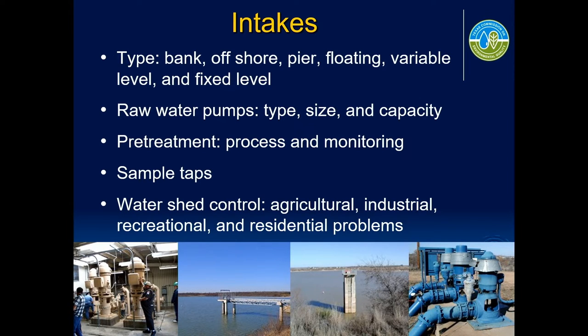Intakes. We always want to start off with the lake. When we look at intakes, we're particularly interested in what type of intake you may have. There are various kinds: intakes located on the bank, offshore intakes, intakes on piers, floating intakes, variable level intakes, and fixed level intakes. It's important what type of intake you have and whether it's functional mechanically. If it's a multi-level intake, can you open all the gates? Is the bottom half of the intake silted in? We're also interested in raw water pumps — what type you have and the size and capacity available at the intake.